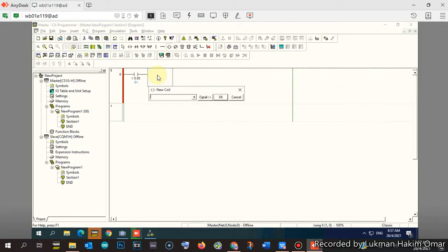In the slave PLC, you cannot directly put 100.0. Let's say I want to turn on output number 7. I cannot do this because this address only exists in the slave PLC. So we have to use an intermediate bit to communicate with the slave. Where does that intermediate bit come from? It actually comes from area number 1. As you remember, area number 1 is start.